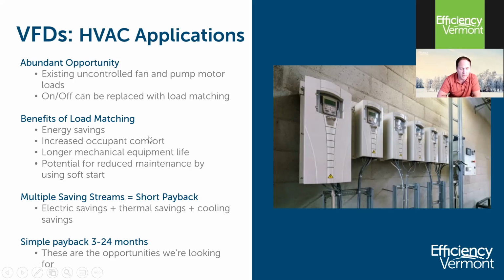Of course, reduced motor speed equals reduced heat. That gives life back to the equipment. And VFDs are an excellent soft starter. They are a better soft starter than a soft starter. Which is why the utilities on larger motors like snowmaking pumps require drives for the soft start capacity on big snowmaking pumps. But that same principle applies to a 10-horse supply fan. It's very different when you slowly ramp up a motor versus banging it across the line. You'll go through less contactors.